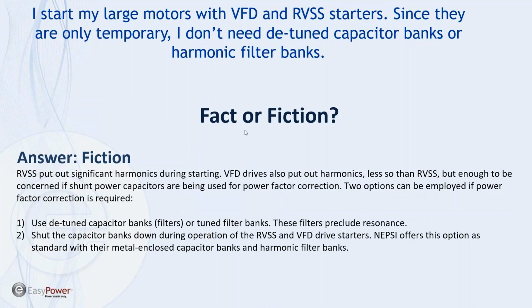So another one is: I start my large motors with VFD drives and reduced voltage soft starters. Since they are only temporary, I don't need detuned capacitor banks or harmonic filter banks. Fact or fiction? Strictly speaking, from an IEEE standpoint, if you're going to start those drives, you do not need to worry about exceeding those limits. But the fact is that if you have capacitor banks in the system and you're starting those drives or reduced voltage soft starts, during the starting periods, which may last from a few seconds up to a minute, the VFD drive and reduced voltage soft starters are putting out a significant level of harmonics. Those harmonics can interact with the capacitor bank and cause resonance issues.